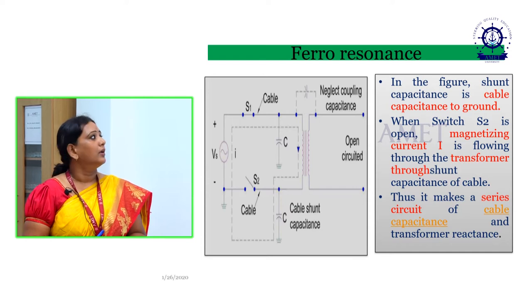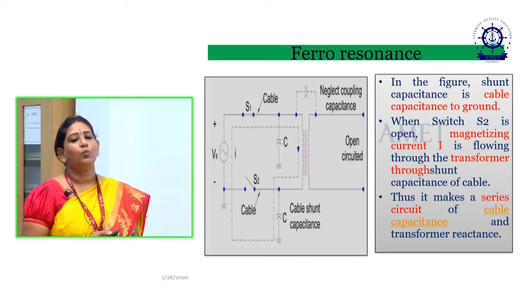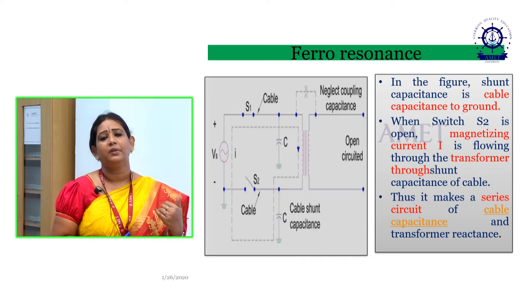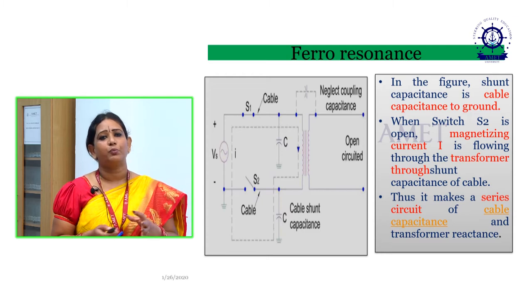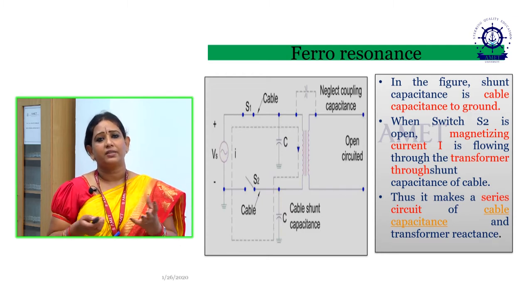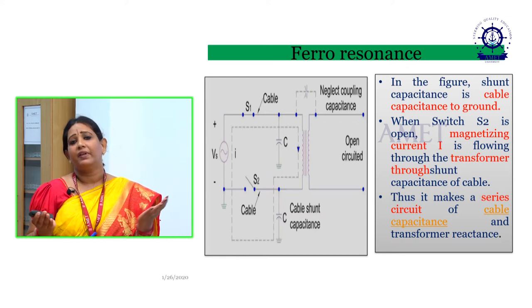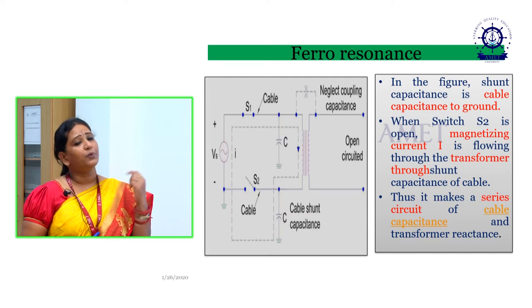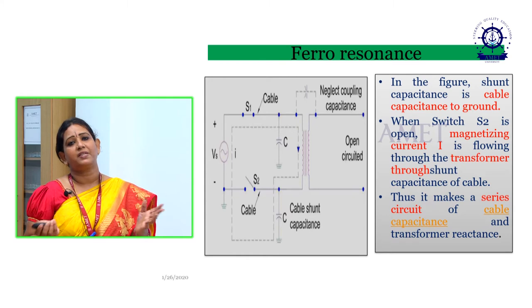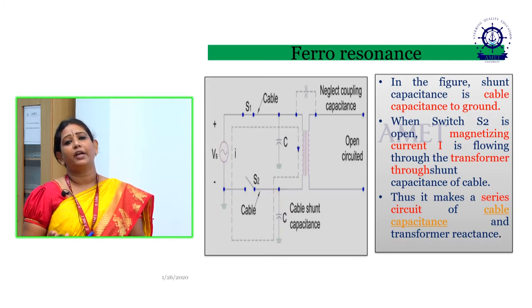Next is a very important overvoltage generation, which has to be taken care of, and we need to know the phenomenon behind it and how ferroresonance occurs, because everyone wonders what ferroresonance is, and they quite confuse it with normal resonance. In a normal network, say a 50 hertz system, a resonance occurs when the inductive reactance is equal to the capacitive reactance. But what is ferroresonance? Ferroresonance basically occurs in major power systems, say a high voltage system, an extra high voltage transmission line. We can experience this type of ferroresonance.